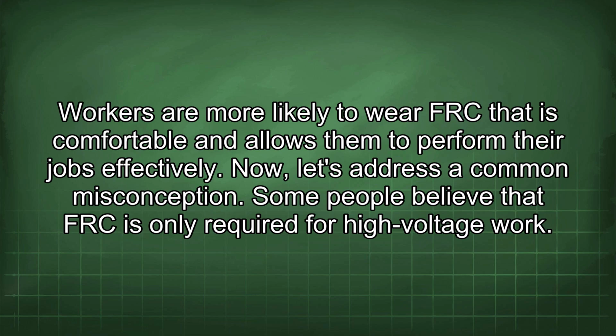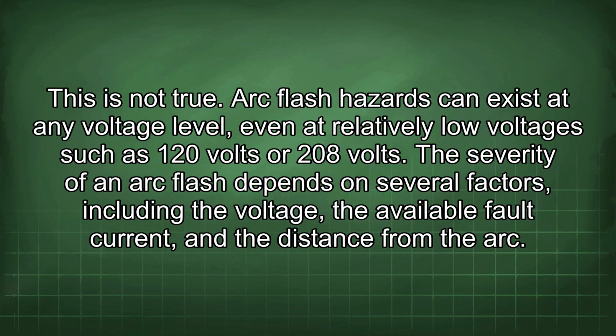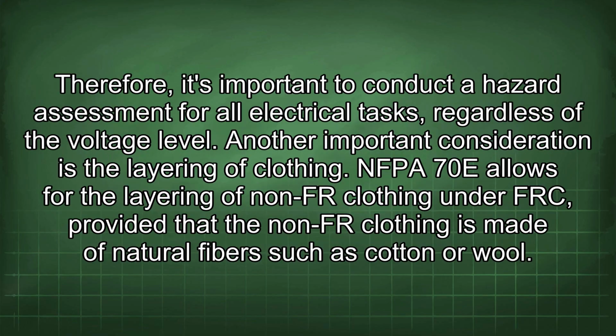Now, let's address a common misconception. Some people believe that FRC is only required for high voltage work. This is not true. Arc flash hazards can exist at any voltage level, even at relatively low voltages such as 120 volts or 208 volts. The severity of an arc flash depends on several factors, including the voltage, the available fault current, and the distance from the arc. Therefore, it's important to conduct a hazard assessment for all electrical tasks, regardless of the voltage level.